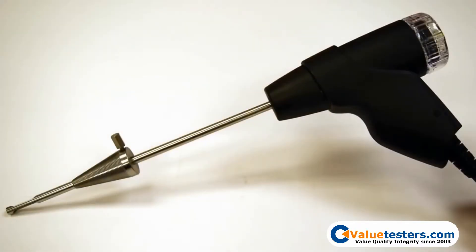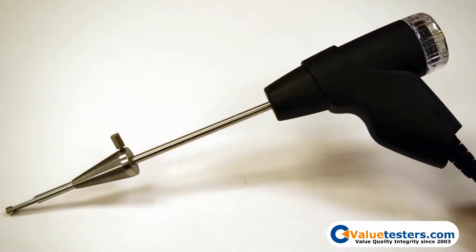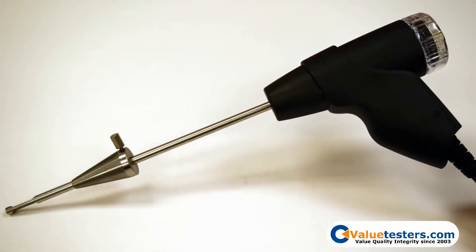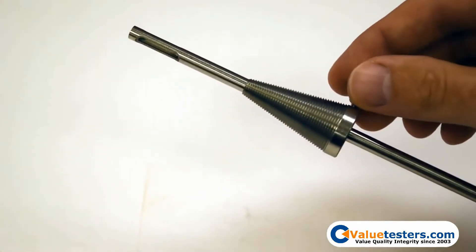On your flue gas probe, there is a probe cone. This cone allows for the flue gas probe to be properly seated into the flue gas duct.